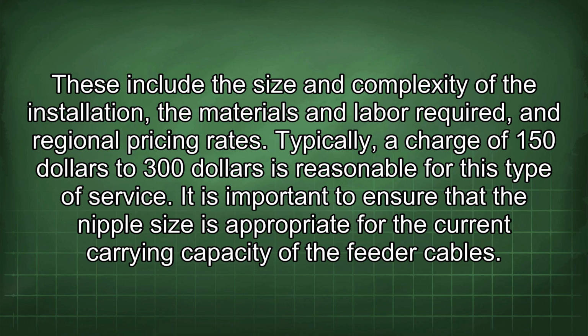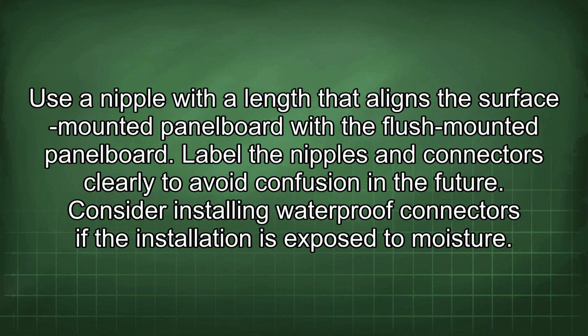It is important to ensure that the nipple size is appropriate for the current carrying capacity of the feeder cables. Use a nipple with a length that aligns the surface-mounted panel board with the flush-mounted panel board. Label the nipples and connectors clearly to avoid confusion in the future. Consider installing waterproof connectors if the installation is exposed to moisture.